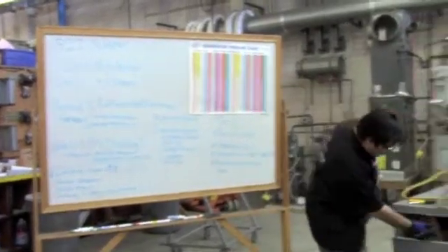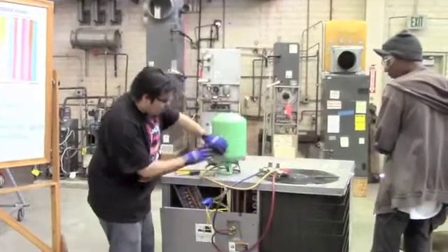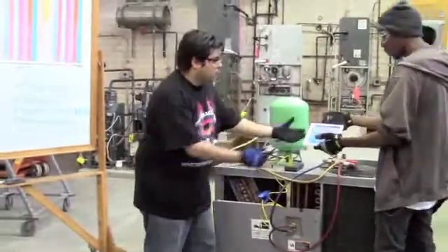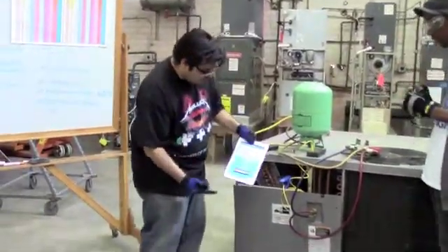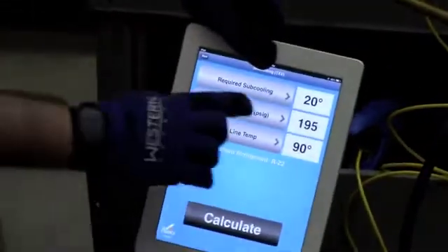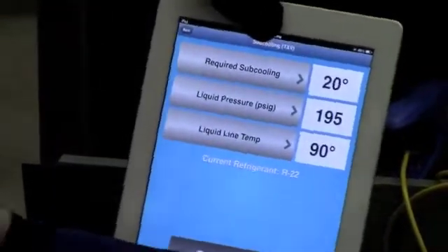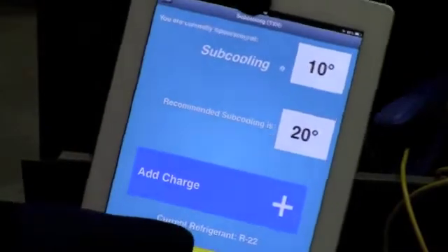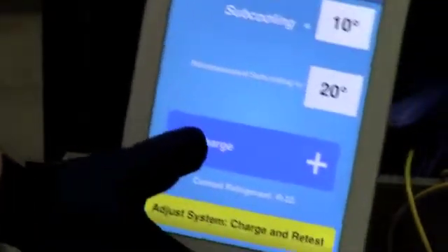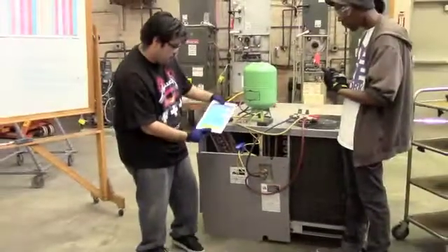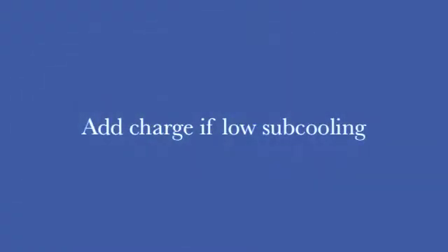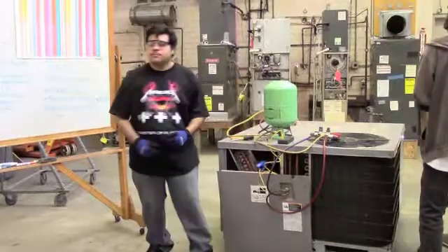So, we put in our clamp. We clamp it on the liquid line. And we physically measure the temperature. So, we get our app and we put in the variables. We put in our required subcooling provided by the manufacturer, our liquid line pressure, and our liquid line temperature. And we just click calculate. And right here, it will tell me how much subcooling I need and how much subcooling I have. And it will either tell me to add or subtract.